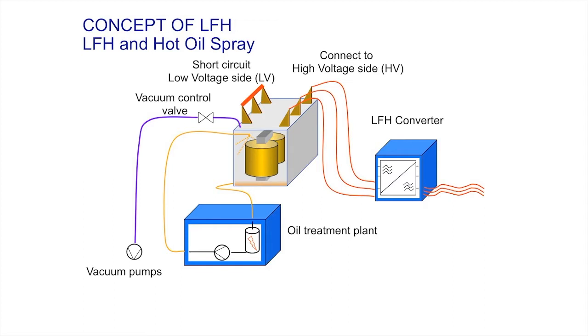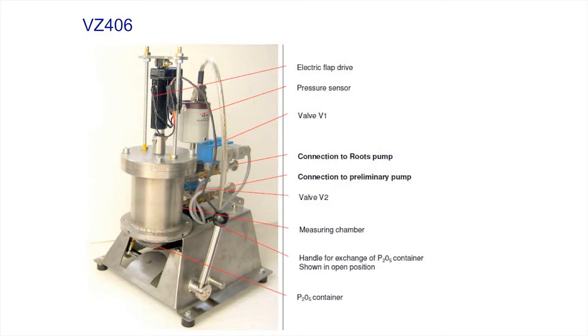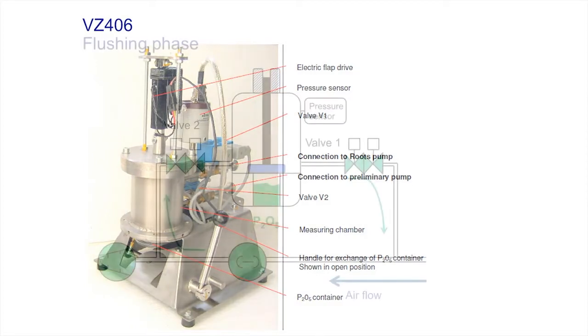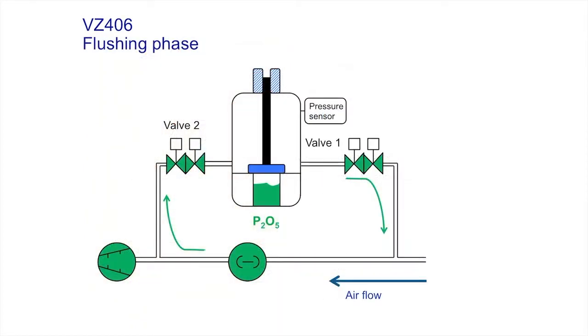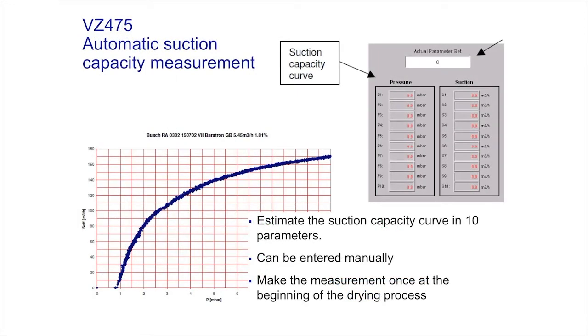The extraction of the water is done by heating the windings with low-frequency current and by heating the insulation with oil circulation. Vacuum is applied to the transformer to extract the maximum amount of water. There is a measurement device for the specific water extraction installed in the oil treatment plant and incorporated in the control software. This device is called VZ406 and works together with the pump suction capacity measuring device called VZ475.